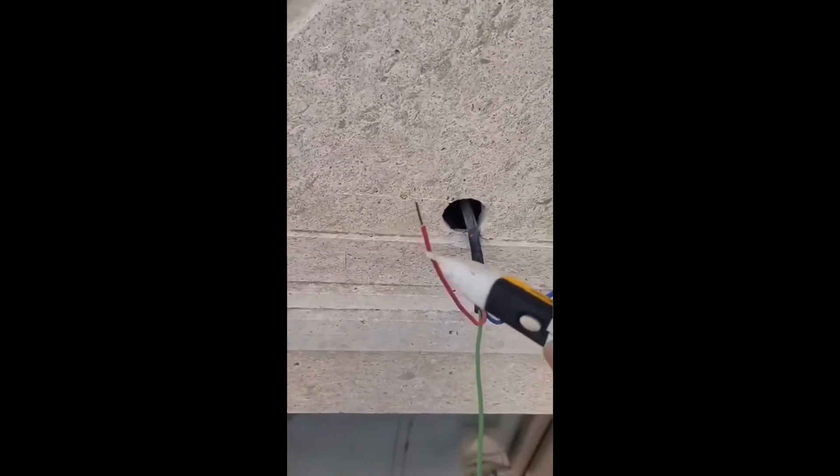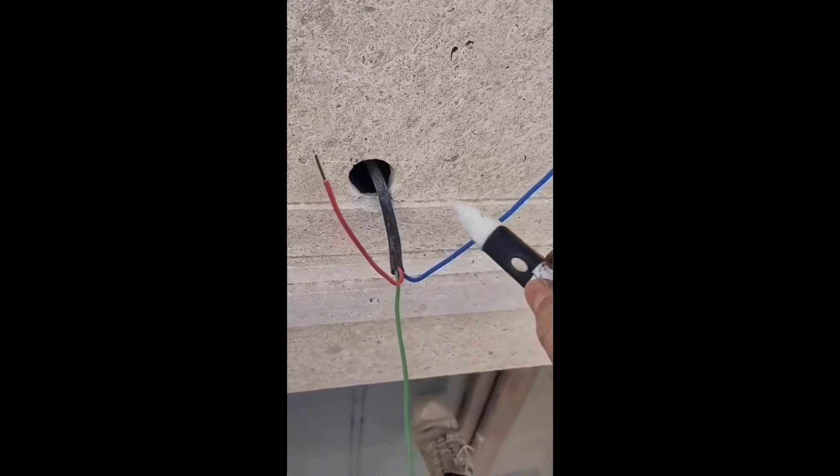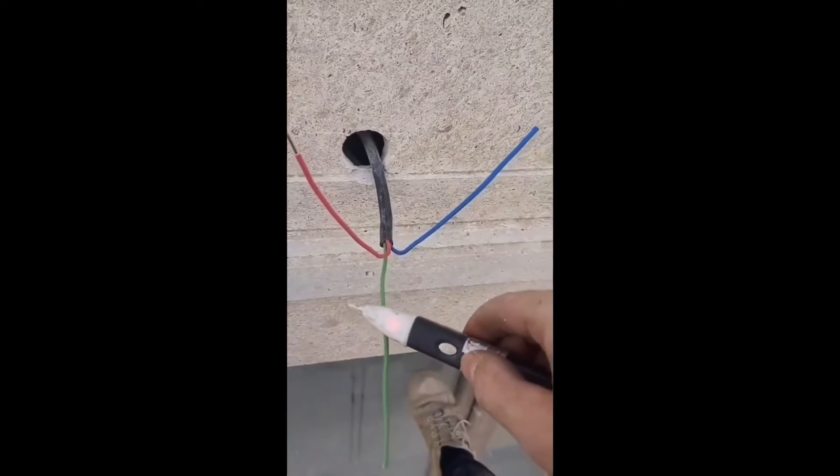That's why tick tracers are not dependable. What this guy's doing, he's reading on a wire. Who knows what's inside the wall? If that wire's coming out of the back of a receptacle, a switch box, something with multiple circuits in it that are hot, he might be reading off of a neutral. Those are different goofy colors — it wasn't even white or black or whatever to make it understandable, at least in America.